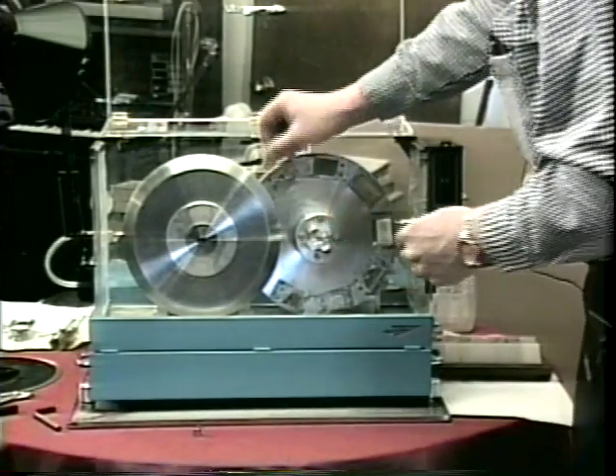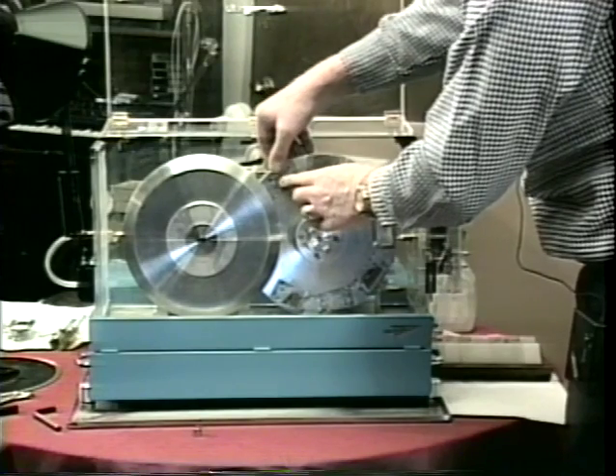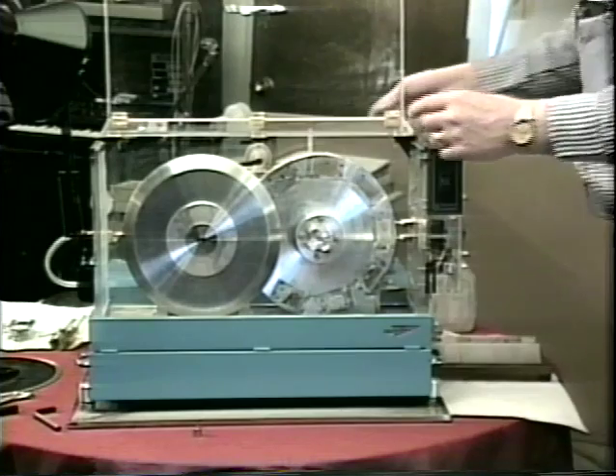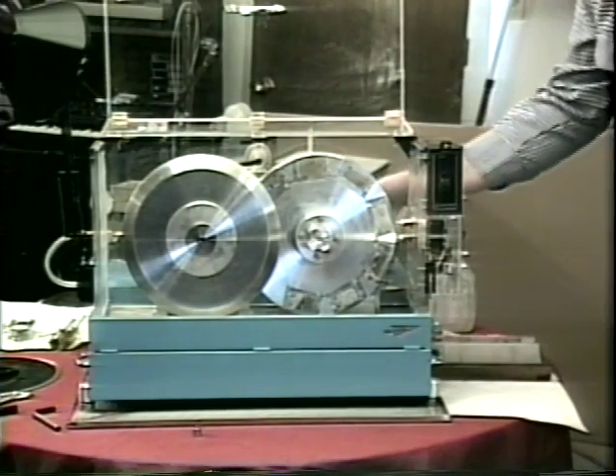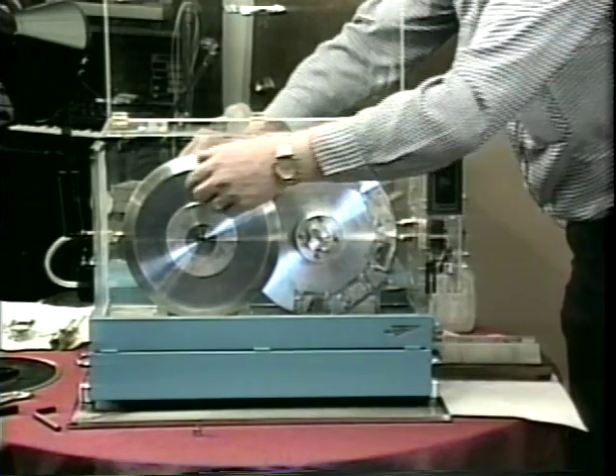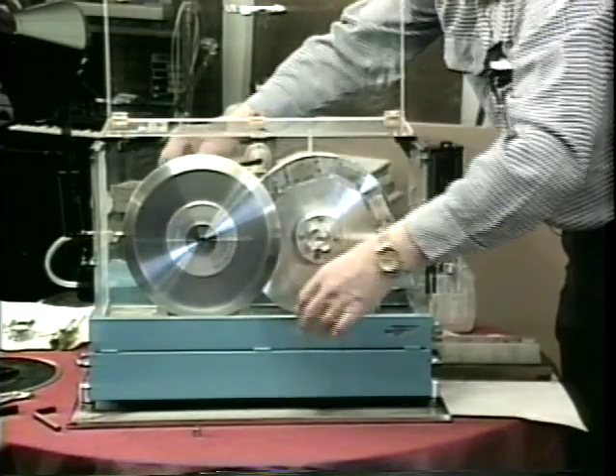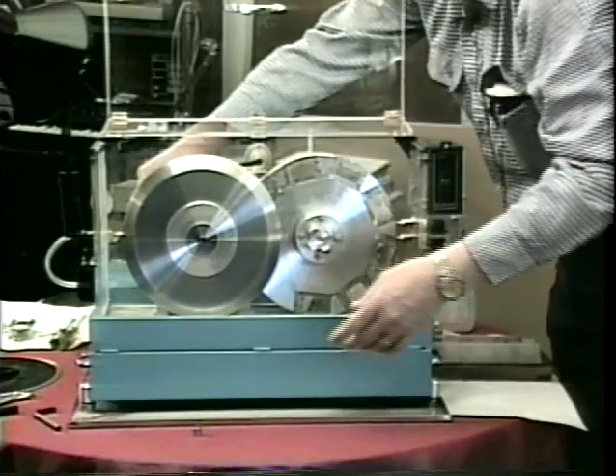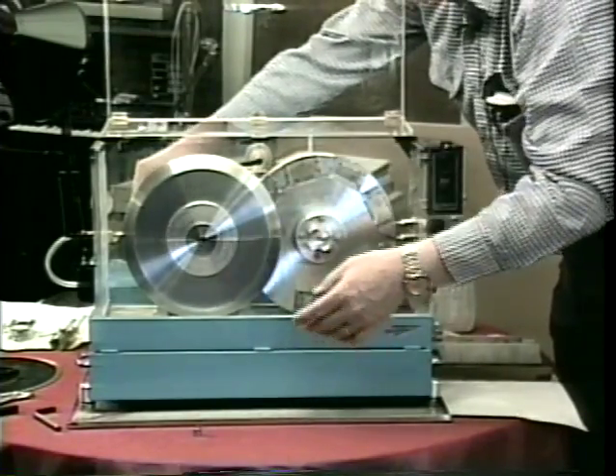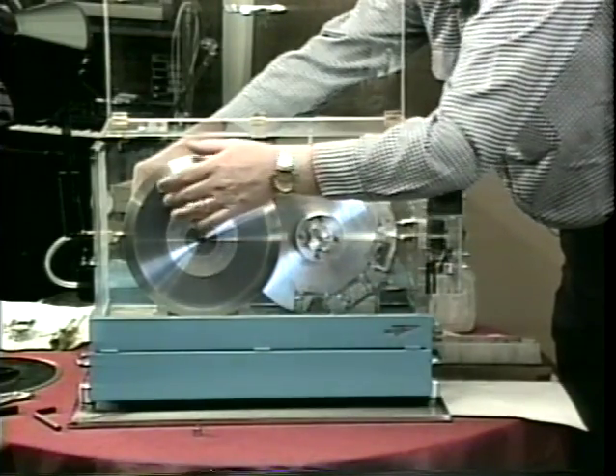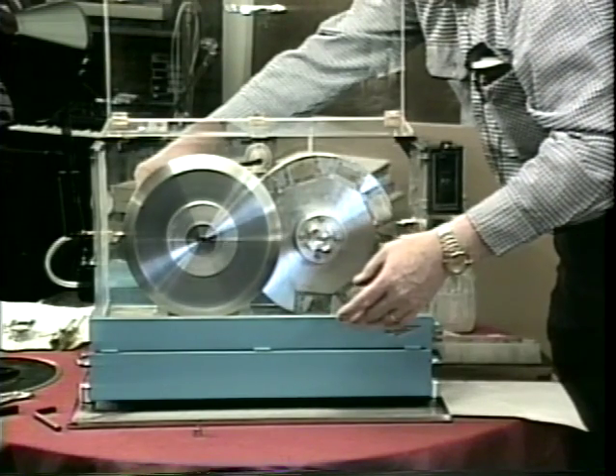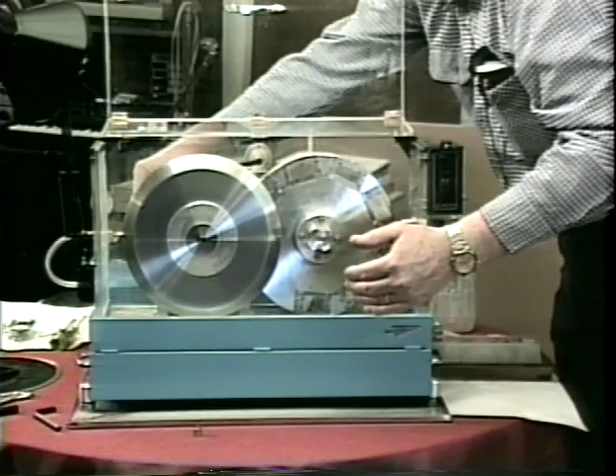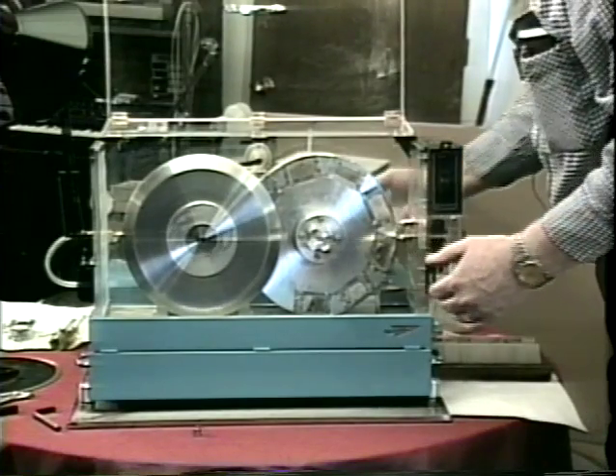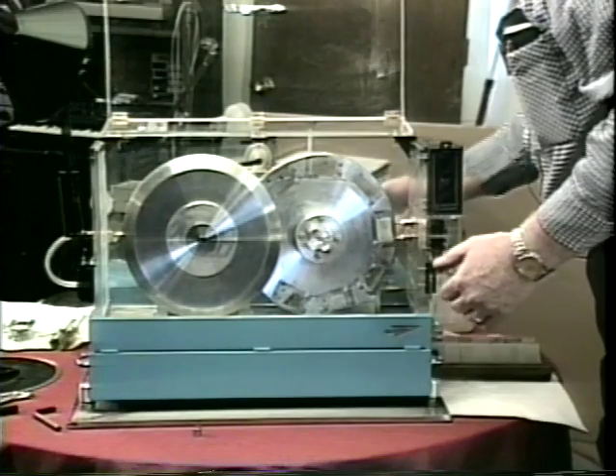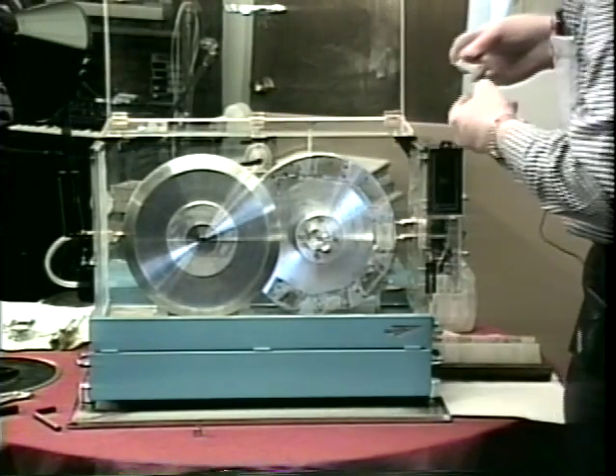To check our dial indicator, we'll replace the slide in number 1 station face, and we'll advance the chuck so that station face is halfway behind the diamond plate. And we'll rotate the diamond plate and bring the diamond plate closer to check our referencing on the dial indicator. There it's going to 0, plus 1 turn, plus 2 turns, and it's just touching right at that point. We'll back this slide away to clear the specimens, and replace it with the number 1 thin section.